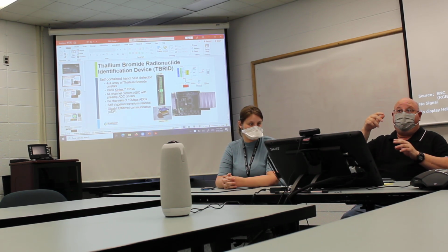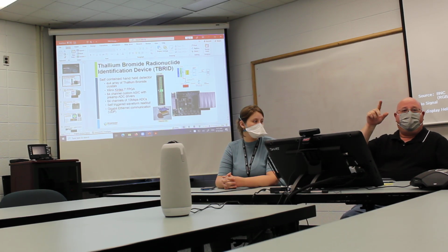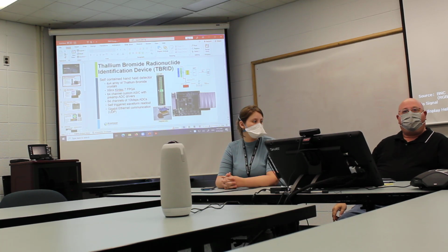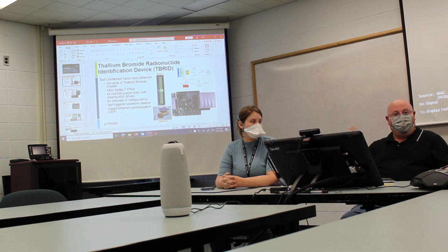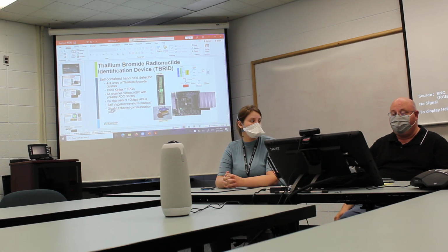And so we can see the location in the X and Y. The Z-axis is given by the anode and cathode. So with the 3D, once we know where that interaction occurred, we can actually make a correction file. And so with a source, this way we can use the thallium bromide to give us an accurate result on the energy being deposited inside that thallium bromide crystal.